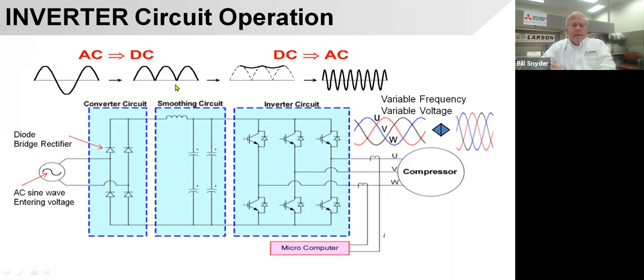Now, if you put a meter on it at that point, you would probably not see it being choppy, because remember, this is 60 cycles between here and here a second. So this is almost doubling that. So we've now gone to like 120 cycles. So on your meter, you'd never see that. You just trust me, it's a little bit of a choppy signal coming out of here.